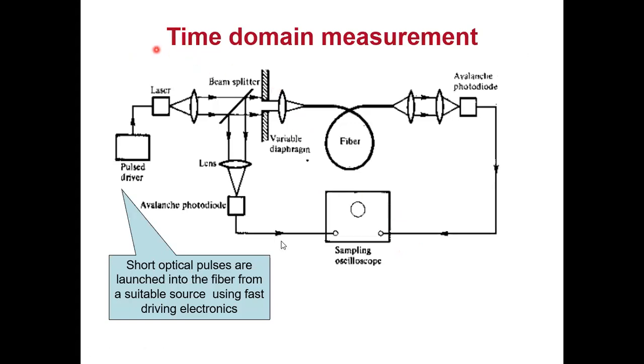You should not be shocked with this setup because we have already done the attenuation measurement, so it is a little bit similar. What we have is a length of fiber, and I have the input light source. I have to send that light through the fiber. When I'm sending the light through the fiber, I require some launch condition. Directly I cannot launch into the fiber, but here you might see the circuitry at this part is a little bit less complicated compared to the attenuation measurement.